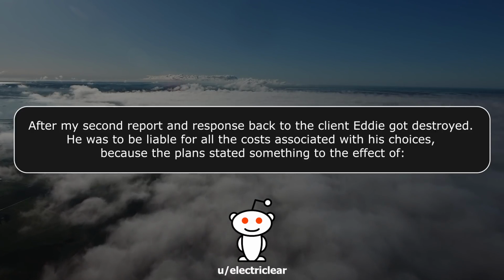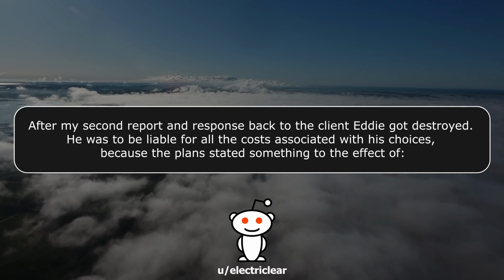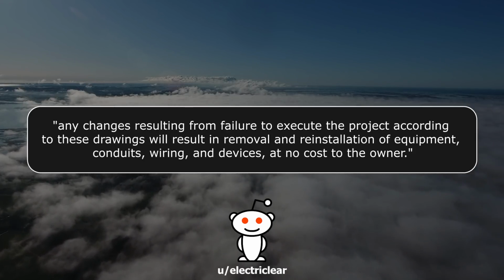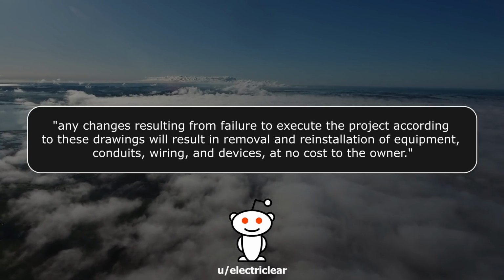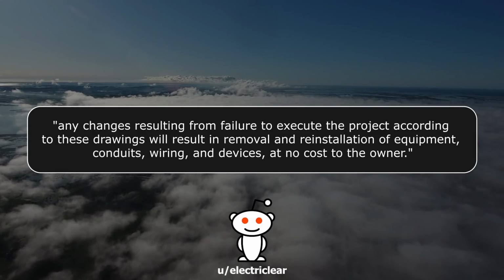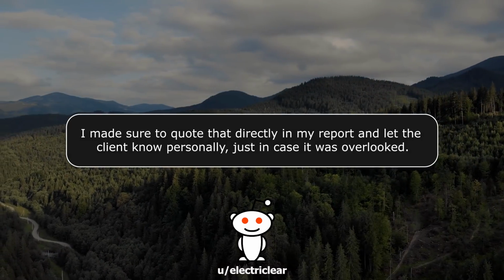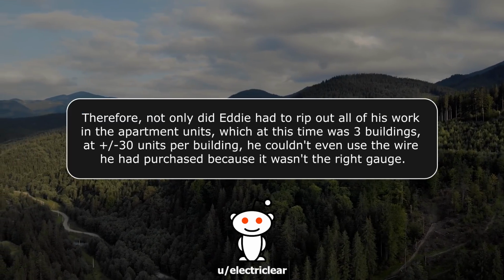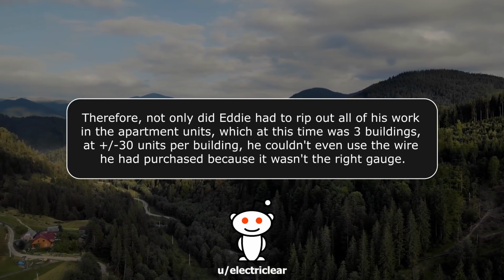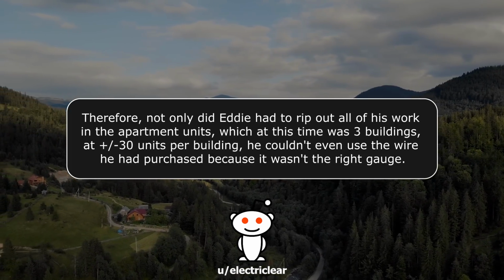After my second report and response back to the client, Eddie got destroyed. He was to be liable for all the costs associated with his choices because the plan stated something to the effect of, any changes resulting from failure to execute the project according to these drawings will result in removal and reinstallation of equipment, conduits, wiring, and devices at no cost to the owner. I made sure to quote that directly in my report and let the client know personally, just in case it was overlooked. Therefore, not only did Eddie have to rip out all of his work in the apartment units, which at this time was 3 buildings at plus or minus 30 units per building, he couldn't even use the wire he had purchased because it wasn't the right gauge.